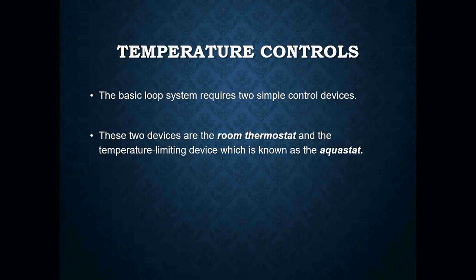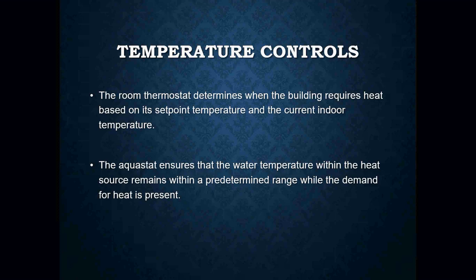The aquastat also tells the burner to shut off when the boiler water reaches a set temperature — say 150 or 160 degrees. Without those two devices, you're going to have a boiler that runs rampant and never shuts off. The room thermostat determines when the building requires heating based on the set point — say 72 degrees. When the room drops below 72, the thermostat closes and sends the signal to the aquastat, which ensures the water temperature within the heat source remains within a predetermined range while the demand for heat is present.